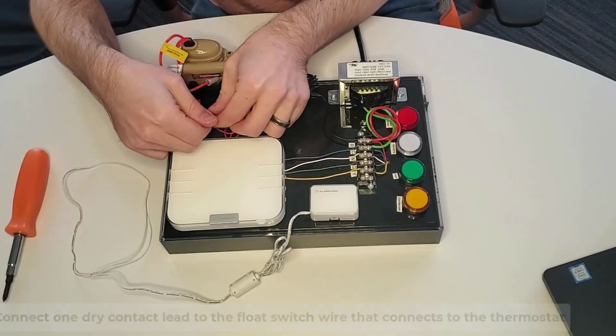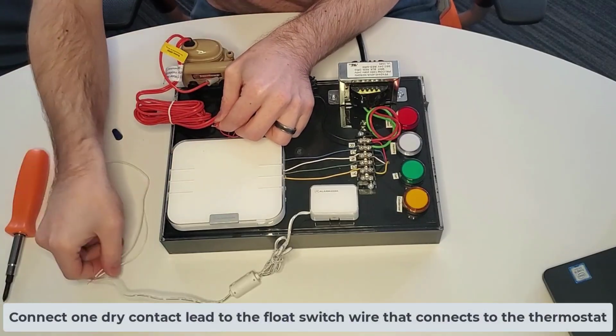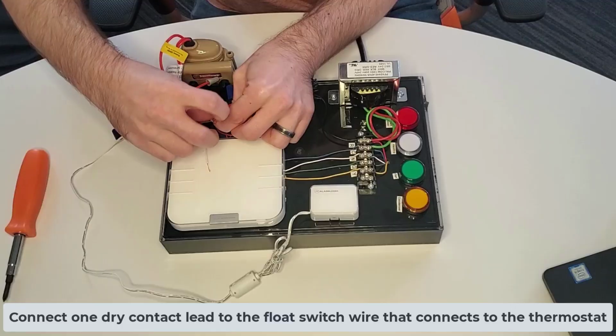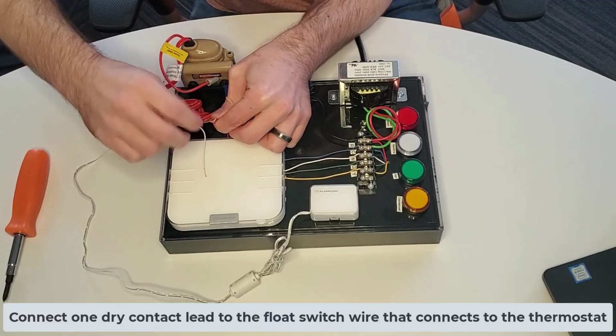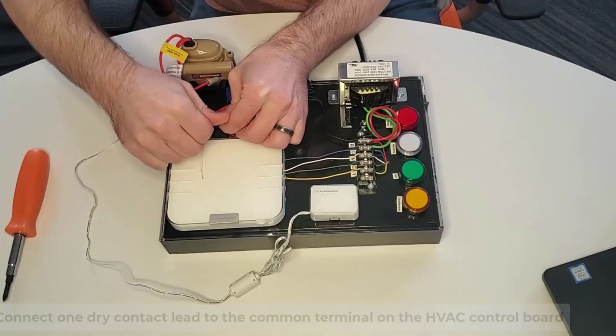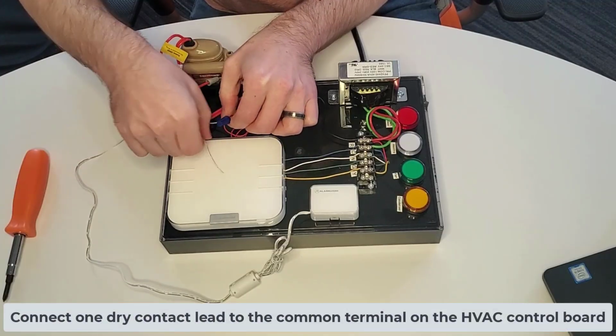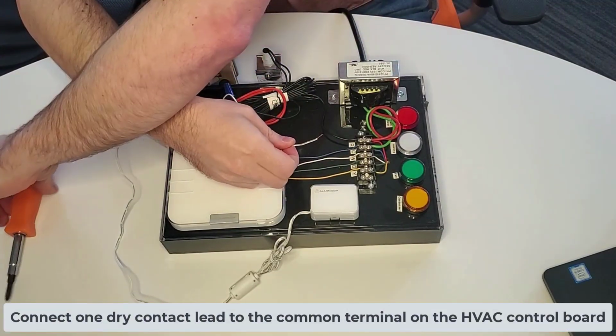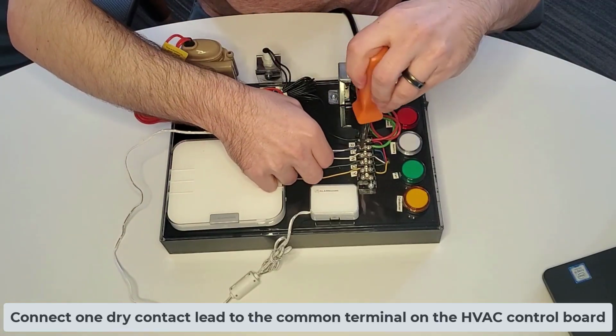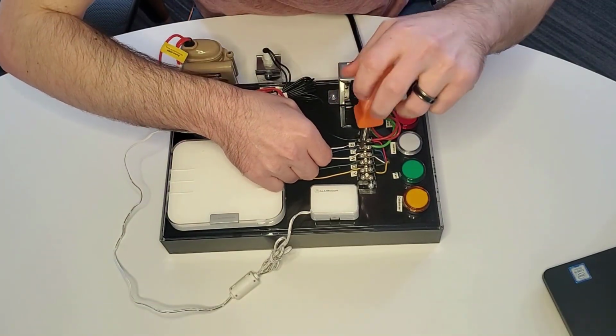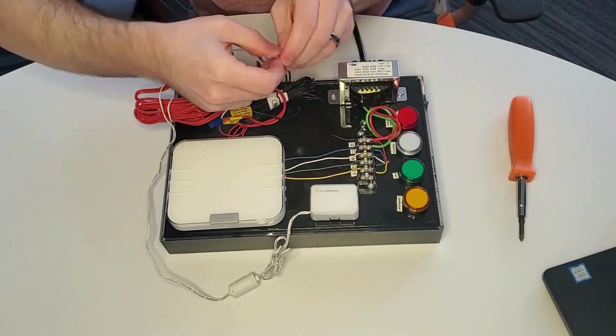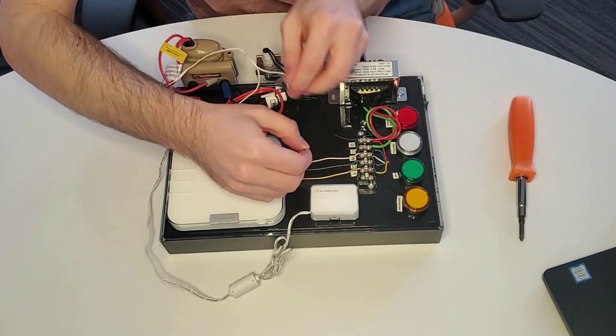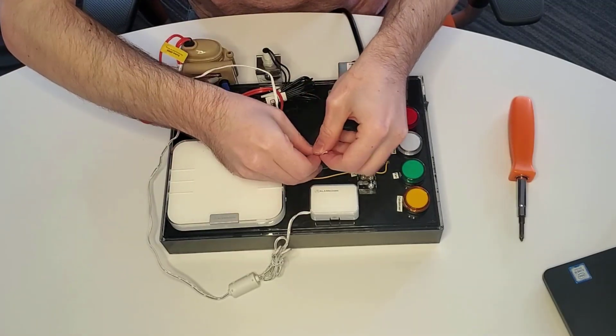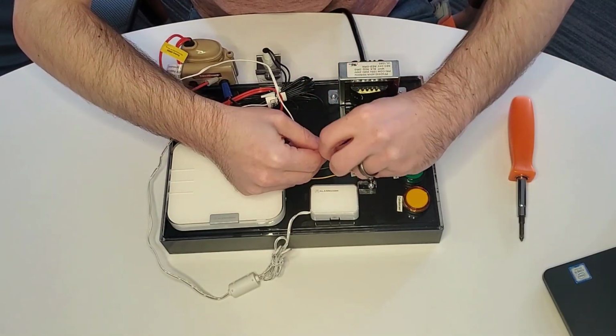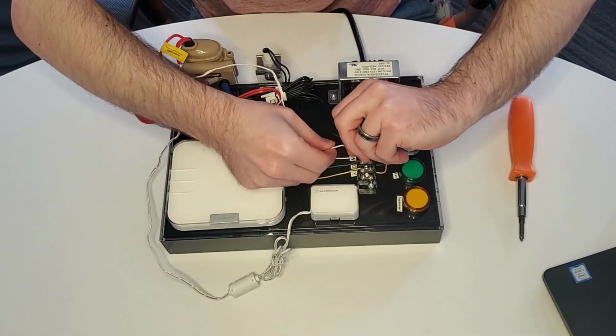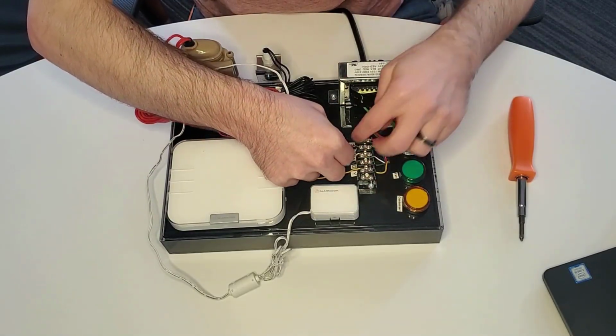To do that, you simply connect one dry contact lead to the float switch wire that connects to the thermostat and one dry contact lead to the common terminal on the HVAC control board. Since the dry contact wire is a lot smaller than the 18 gauge thermostat wire, I usually recommend twisting the 2 wires together to make sure the dry contact wire doesn't slip out during or after installation.